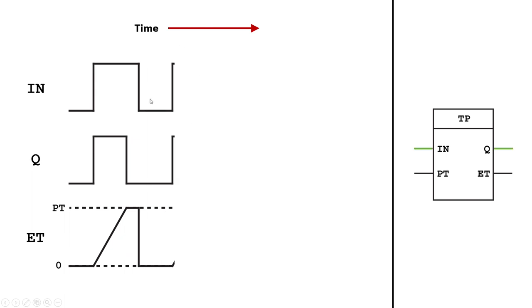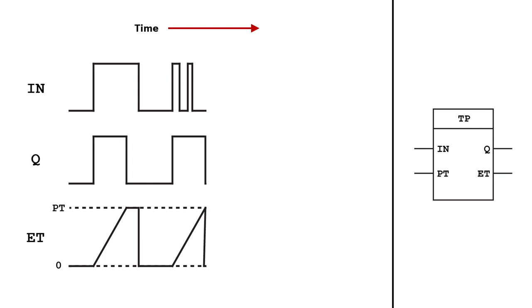Let's try again. I turn on the input, the output turns on immediately, and the elapsed time starts counting because the pulse is active and we want to count its length. Even if I turn off the input, the elapsed time will still count — the pulse will be on for that full amount of time, no matter what. I can turn the input on and off and nothing changes before the elapsed time reaches the preset time. We generate the same pulse of the same length both times.